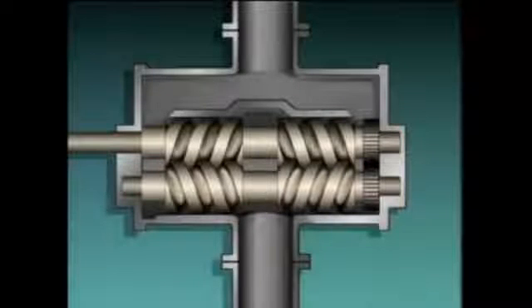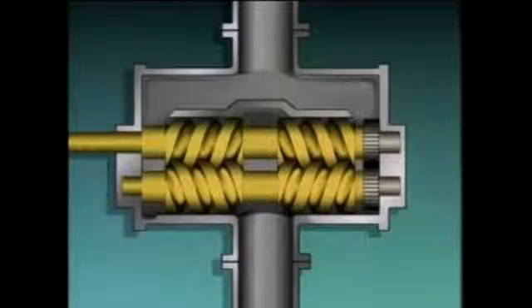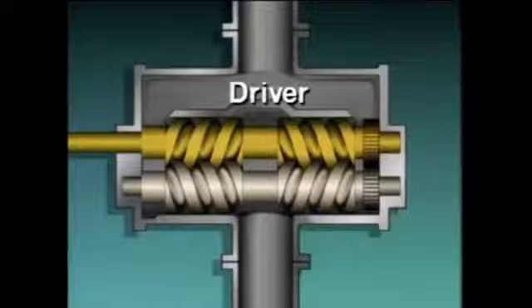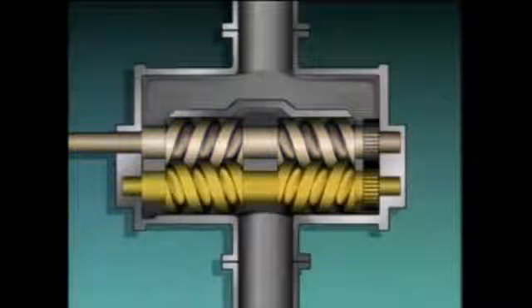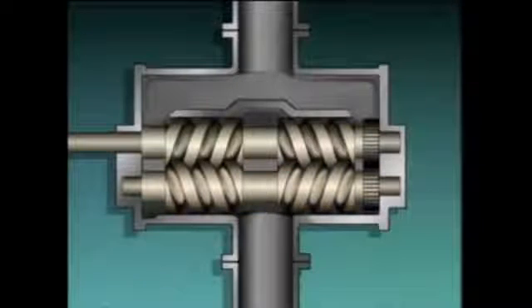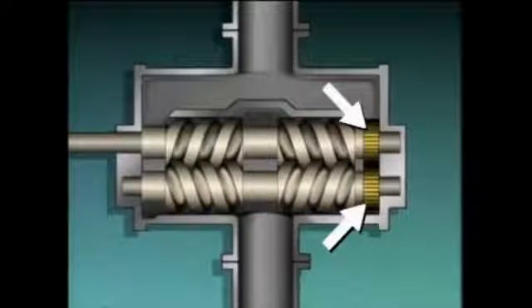Not all screw pumps use a single internal screw. This is a two-screw pump. One of the screws is attached to a shaft that's coupled to the pump's driver — this screw is known as the power or driver screw. The other screw is often referred to as the idler screw. In this pump, power is transmitted from the driver screw to the idler screw through a set of timing gears.